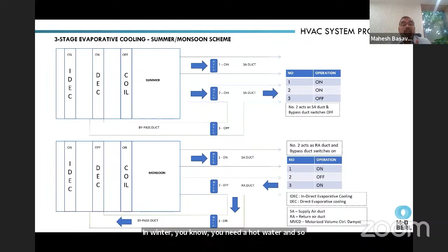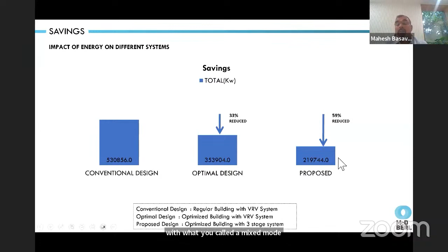It is a mixed mode cooling system or heating system. In winter, you need hot water, and the same chiller can produce hot water. The same chiller can also produce chilled water. So comparing a conventional design versus an optimal design versus what is proposed, we are able to reduce our electrical load by 59% by using a mixed mode cooling system. First we reduced the air conditioning load by 33%. We could have gone with a conventional air conditioning system, but we went with a mixed mode cooling system, which reduces our electrical load by 59%.